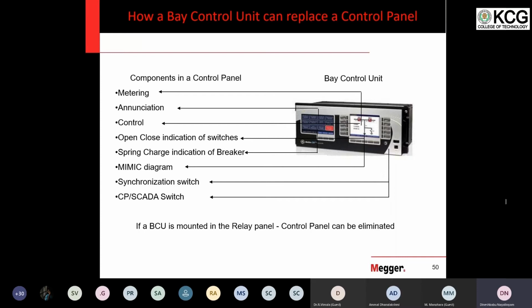The answer is this is a cheaper solution. When we look at replacing one control panel with a bay control unit, it will appear to be expensive. However, just look at the overall cost. Number one, we have eliminated 50 panels. 50 panels consume a huge amount of space. So when the space is reduced, the substation construction cost itself comes down. We may make a smaller control room. You don't need a big control room.